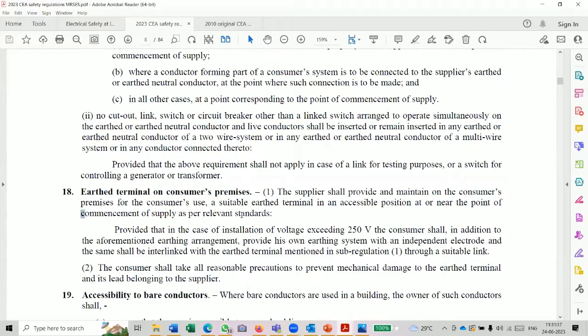And the proviso also, they have introduced some specific classes. That is the last class. And the same shall be interlinked with the earth terminal mentioned in sub-regulation 1 through a suitable link. This is what we call the supplier's responsibility of providing a link, that is, an earth neutral link at the consumer premises. Apart from that, especially for consumers whose voltage exceeds 250 volts. For consumers with higher voltage, they have to use their own earthing system. The two should be interconnected.